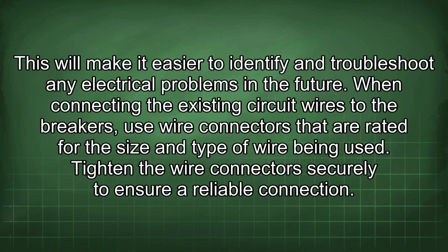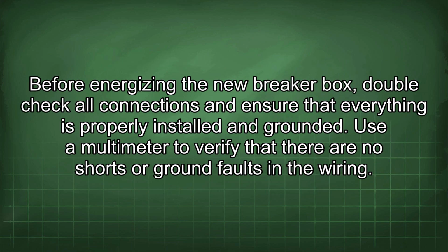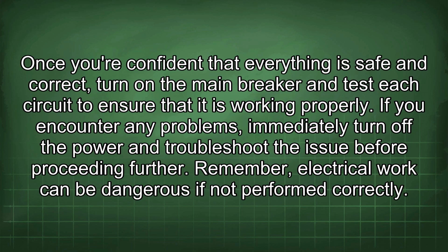When connecting the existing circuit wires to the breakers, use wire connectors that are rated for the size and type of wire being used. Tighten the wire connectors securely to ensure a reliable connection. Before energizing the new breaker box, double-check all connections and ensure that everything is properly installed and grounded. Use a multimeter to verify that there are no shorts or ground faults in the wiring. Once you're confident that everything is safe and correct, turn on the main breaker and test each circuit to ensure that it is working properly. If you encounter any problems, immediately turn off the power and troubleshoot the issue before proceeding further.